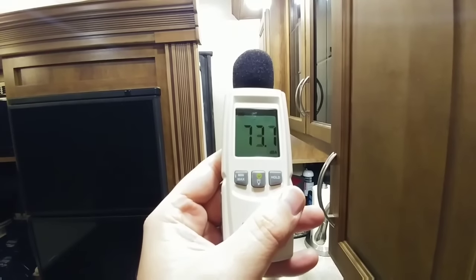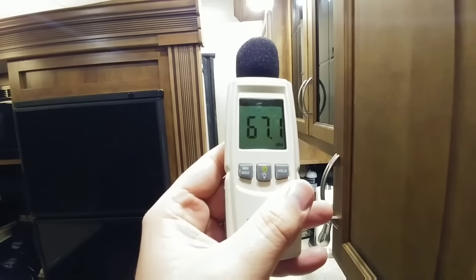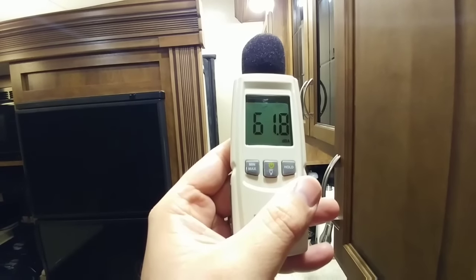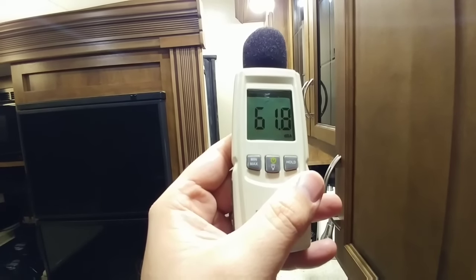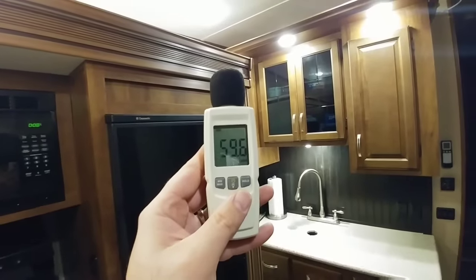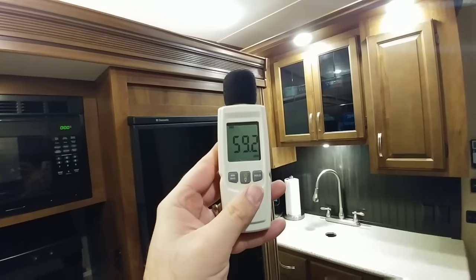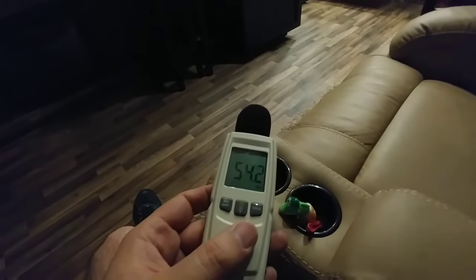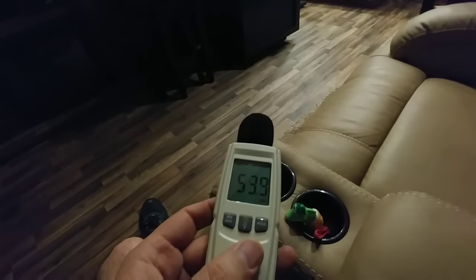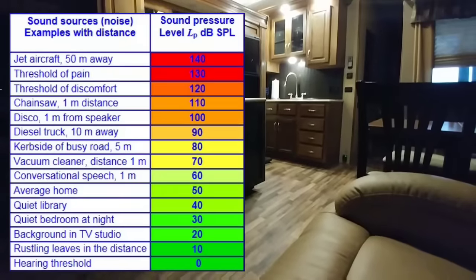From standing right here, this is about the same volume as the air conditioning was before I put the baffle up — I'm standing on the opening side of it. Right at 62 decibels. Now I'm standing underneath it — 59.2. Now I'm sitting down in the living room — roughly 54 decibels. That is a huge improvement.